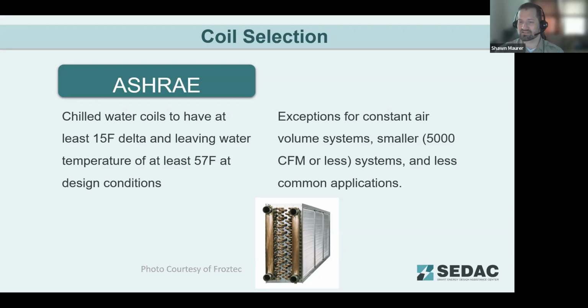Most chillers' capacity is based on a 10-degree differential between supply and return. If there's only a 5-degree difference, which happens in mild conditions with that typical 10-degree design for coils at the air handling units, then a chiller can only put out about 50% of its capacity at rated flow. And so this standard here is taking into account that as we're improving control of systems and taking into account more of the part load factors and efficiencies of systems, trying to maintain overall system efficiency. And so requiring that greater temperature difference for the coil design at your air handler is helping to improve that part load performance of your systems at the central plant.